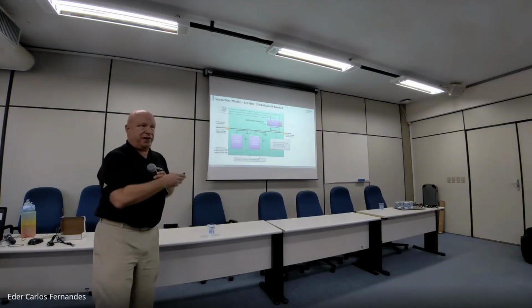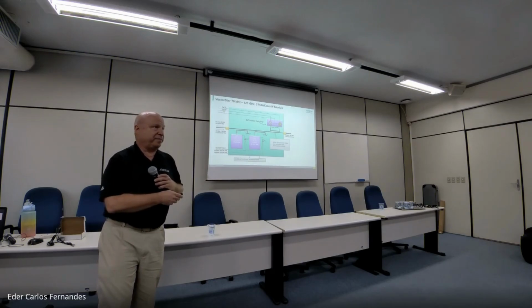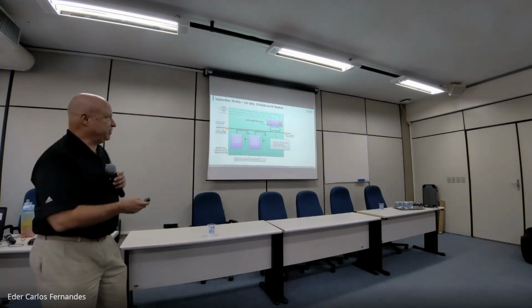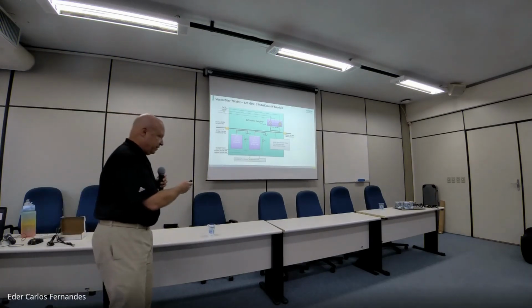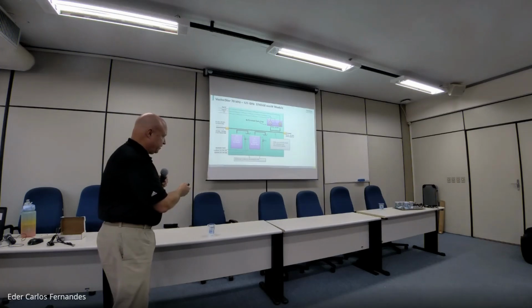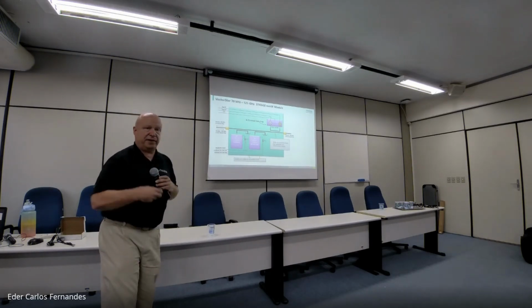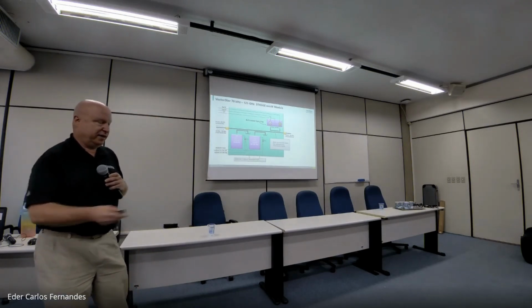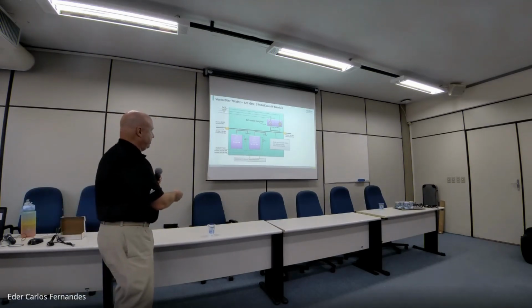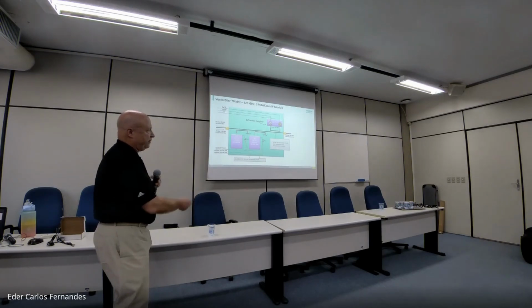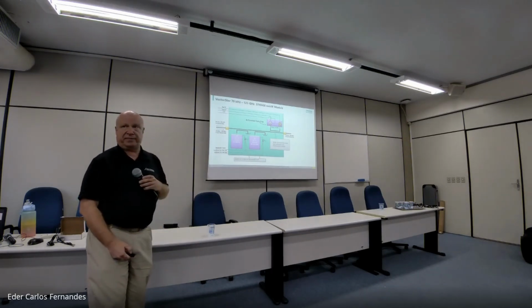Now, inside the module itself, there's a lot going on. And as I mentioned, we're not only up-converting or multiplying our source. You can see 2 bands of multiplication taking place. We're also passing through the signal from low frequencies up to 54 gigahertz. So we have a break frequency at 54. Then we go through the multipliers up to 80, 80 to 125, and then right out through the test port here. That's the 1 millimeter interface on the module.